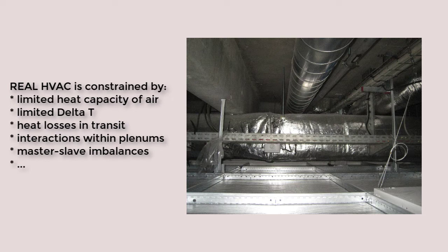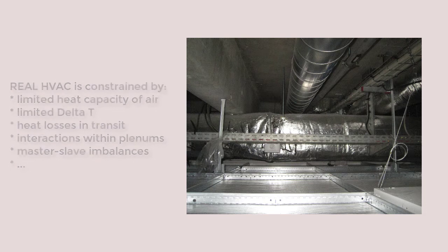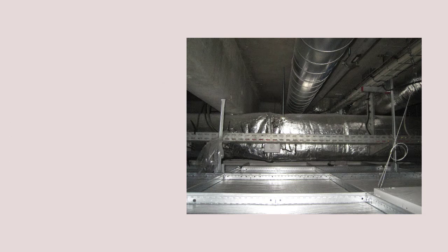A single air handler may deliver to several rooms, and thus we are confronted by the classic issues of master-slave controls. If we use ceiling voids as plenums, then we're dealing with an aggregate of temperature, humidity, and contaminants from multiple return grills. The mass of the floor structure above the ceiling void may also come into play. If we used raised floors and floor registers, similar actions also come into play, complicating the performance of the system.